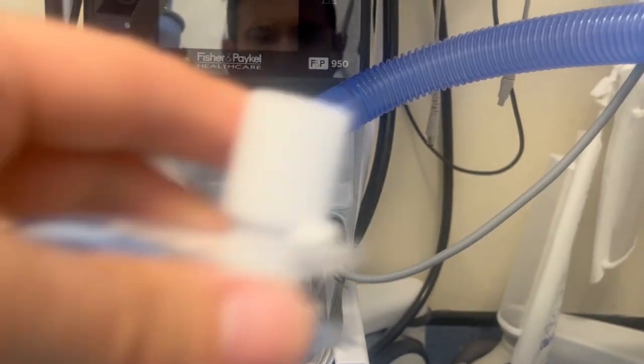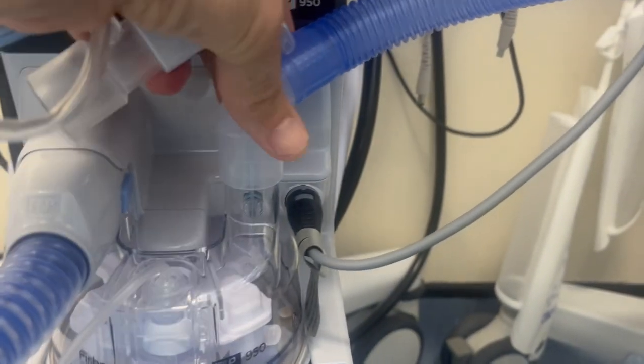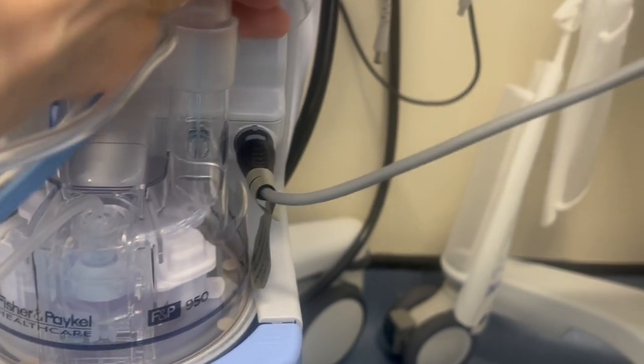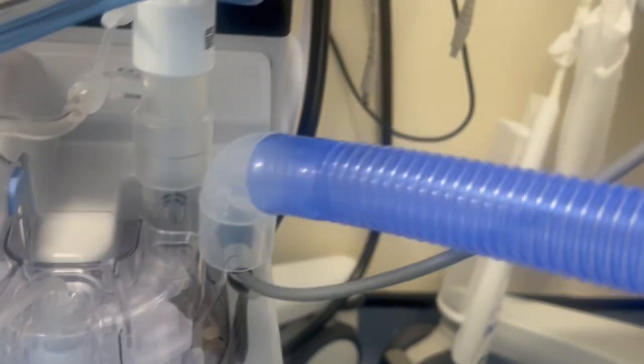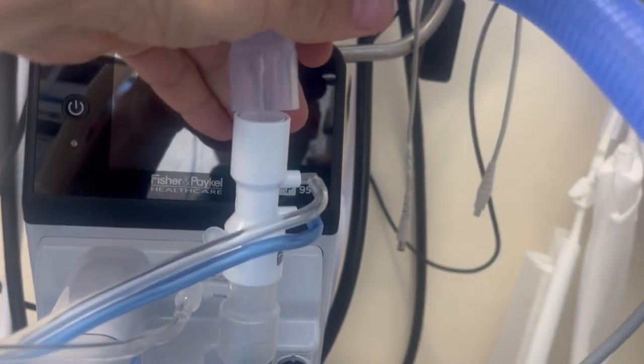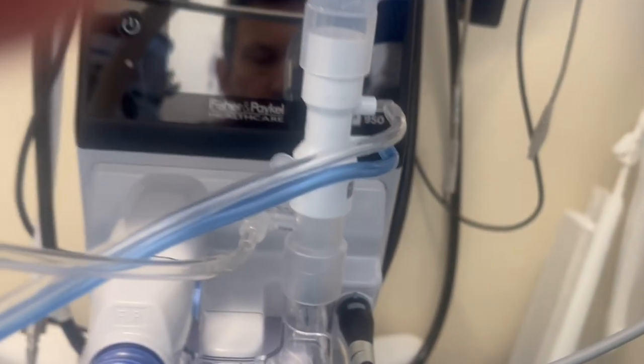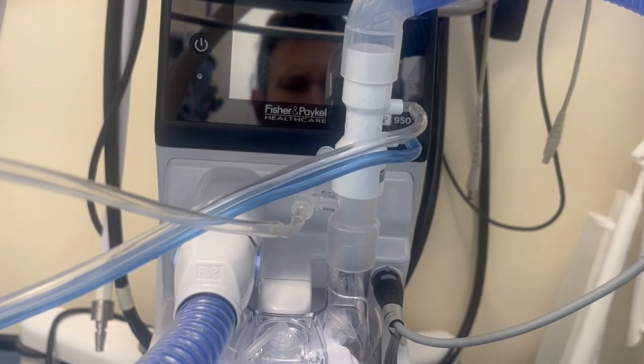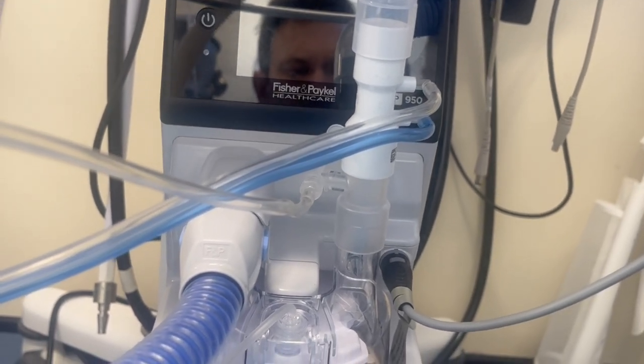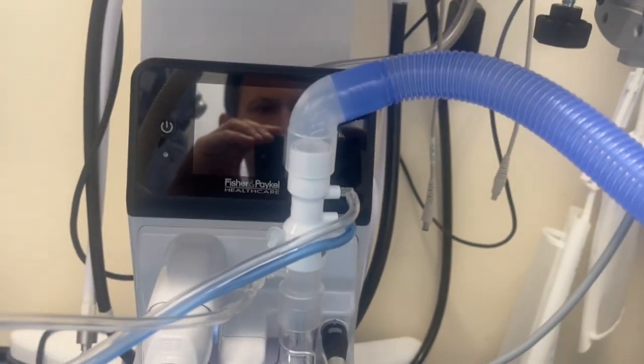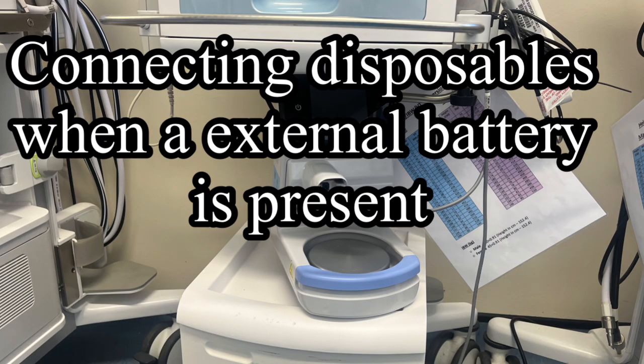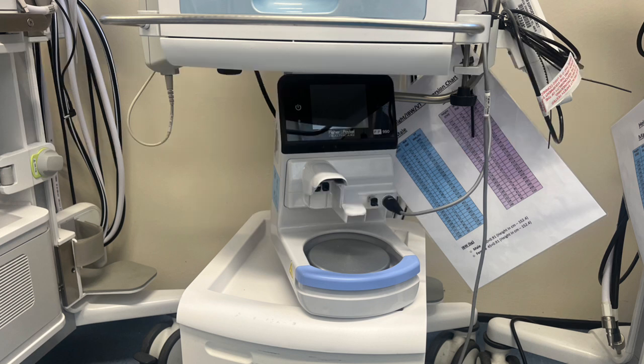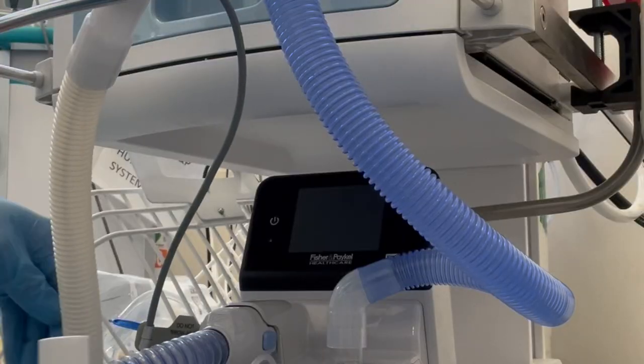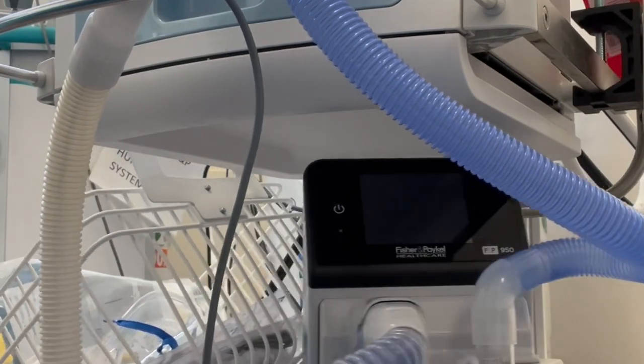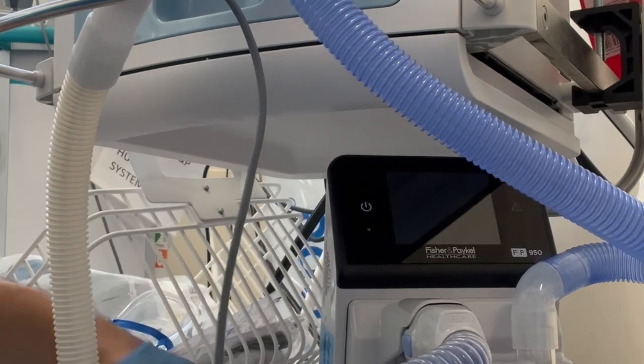If an external battery is not in place, you should have enough room to place the disposables on the humidifier directly under the vent. With the nitric injection line going directly onto the humidifier with the flow measurement line on top of this. The angle piece from the blue tubing that connects the humidifier to the inspiratory port connected to the top of the flow measurement line. The humidifier should be angled to the outside as there isn't much space underneath the vent.